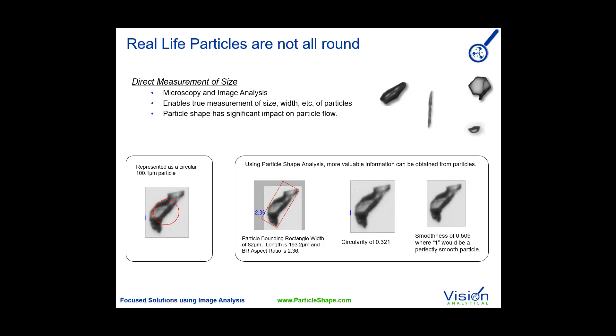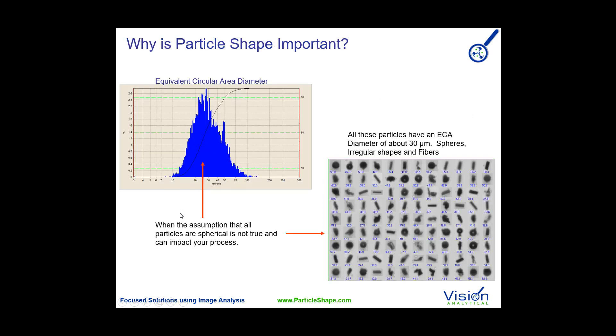That's where direct measurement techniques become more important to the user. When we have direct measurement techniques such as image analysis, we have the ability of actually taking the images of the particles. We can do measurements assuming that they're round, but we can also do direct measurements of their width, their length, aspect ratio, how round the particles are, how smooth the particles are. So you get a lot more information, not just size. This is very important because you can have multiple particles of different shapes, and if you assume that they're round, they're going to give you a false sense of understanding.